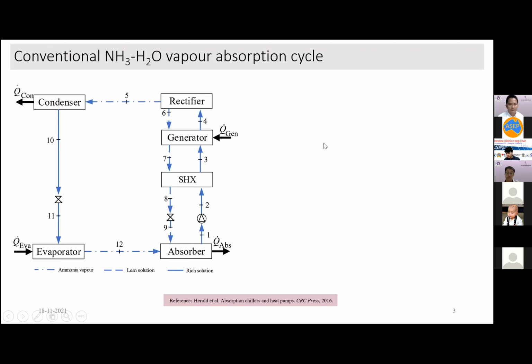This is the schematic of the conventional ammonia water absorption refrigeration cycle, in which the rich solution from the absorber is pumped and preheated in the solution heat exchanger, and the preheated solution enters the generator. In the generator, the solution receives heat from the external source, Q_gen. After the desorption process, the mixture of water and ammonia vapor is driven into the rectifier. The rectifier is a heat exchanger which separates the ammonia and the water, and the pure ammonia vapor enters the condenser, and the saturated water is driven back into the generator.